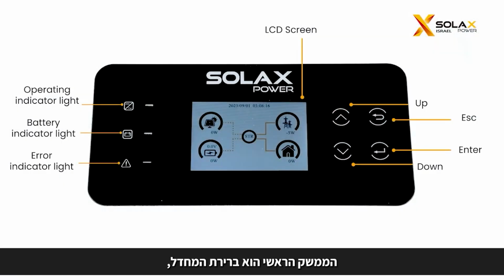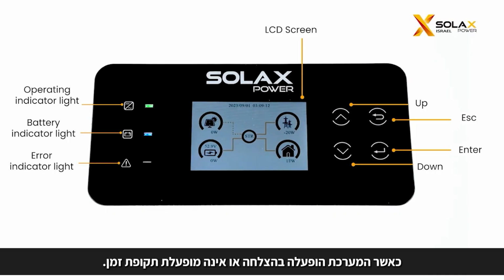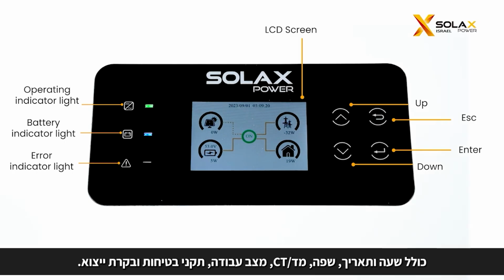The main interface is the default interface. The inverter will automatically return to this interface when the system started up successfully or not operated for a period of time. Next, we will demonstrate how to set the relevant settings on the inverter, including time and date, language, meter/CT, working mode, safety regulation, and export control.